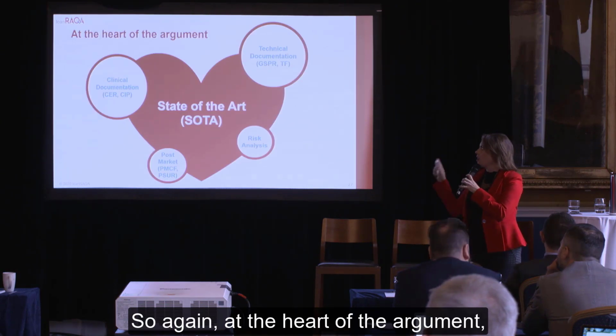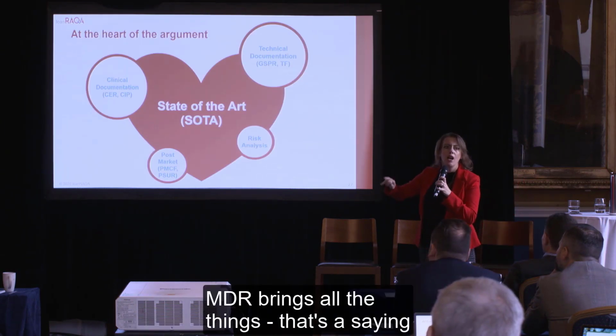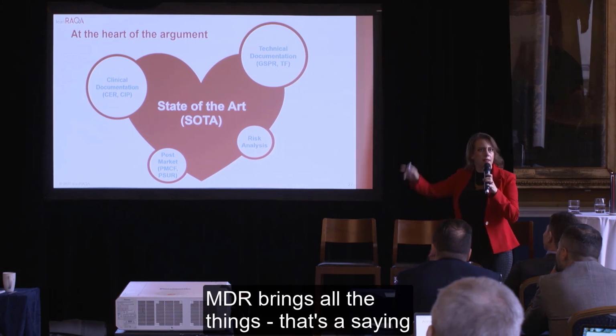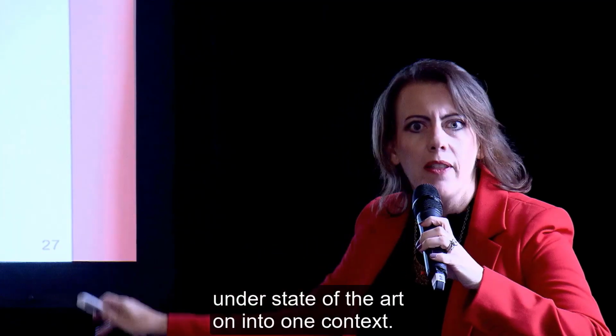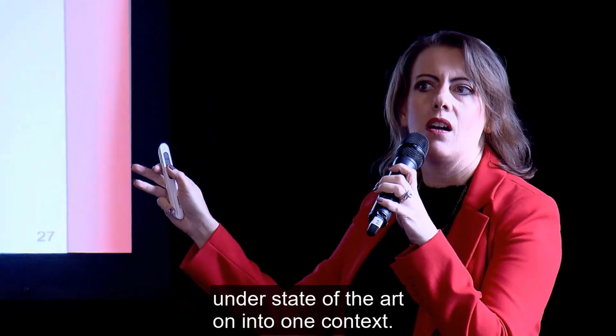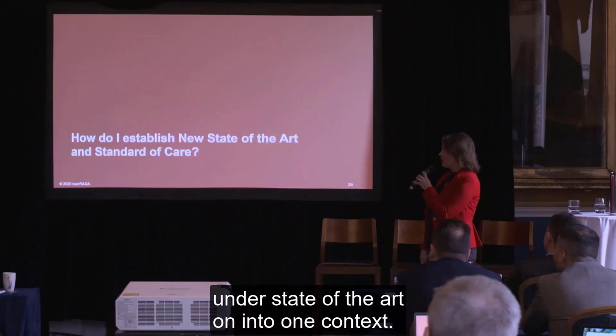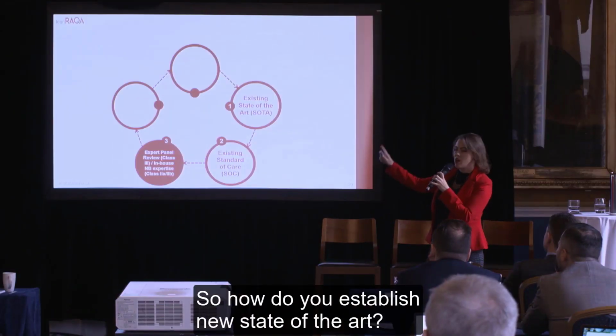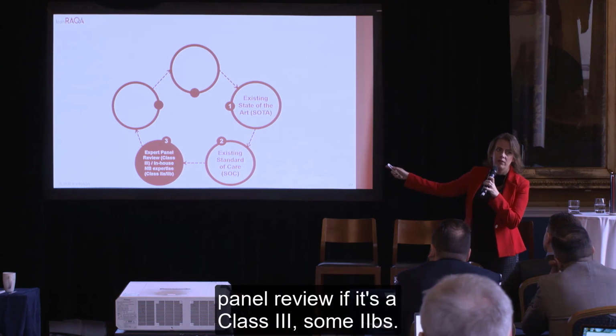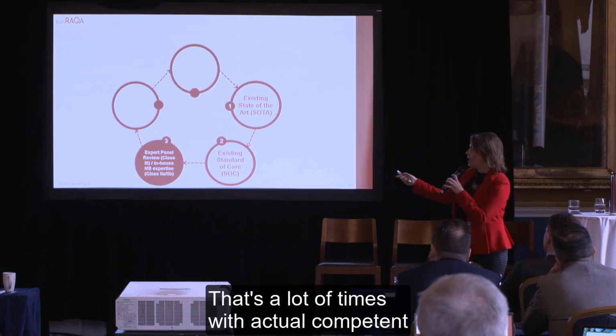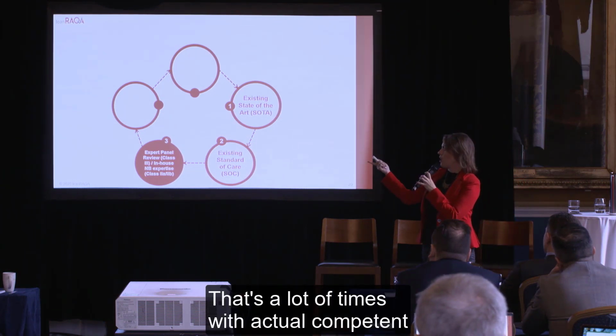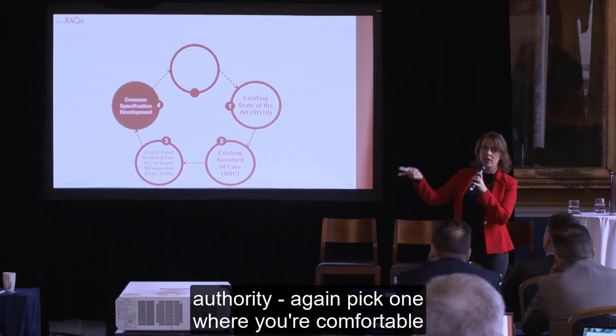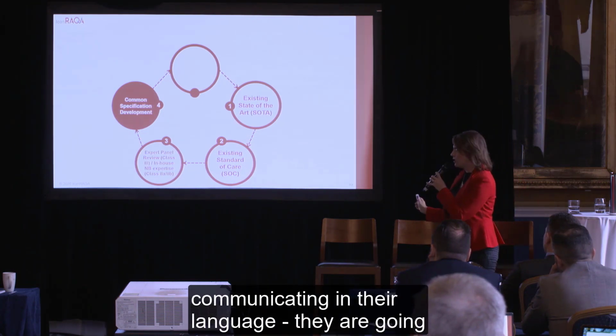So again, at the heart of the argument, MDR brings all the things under state of the art into one context. So how do you establish new state of the art? You're going to have to go through an expert panel review if it's a class 3, some 2Bs. That's a lot of times with the actual competent authority. Again, pick one where you're comfortable communicating in their language.